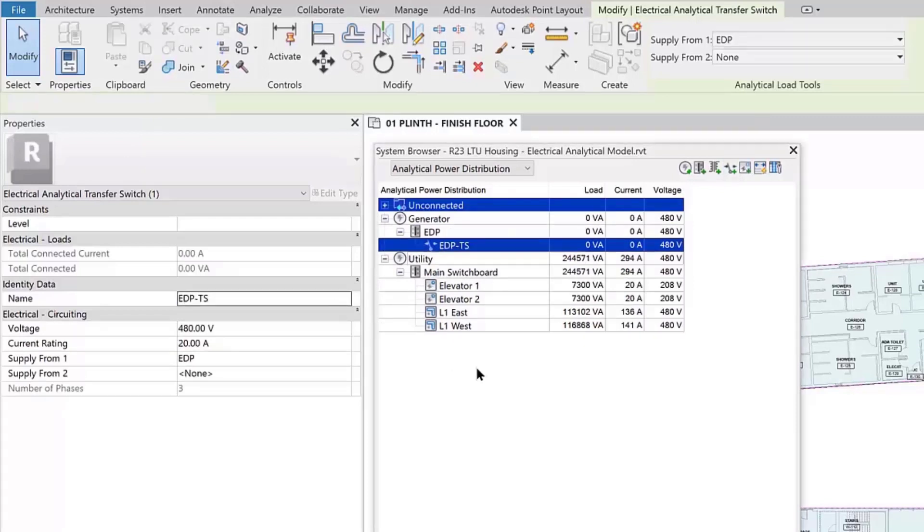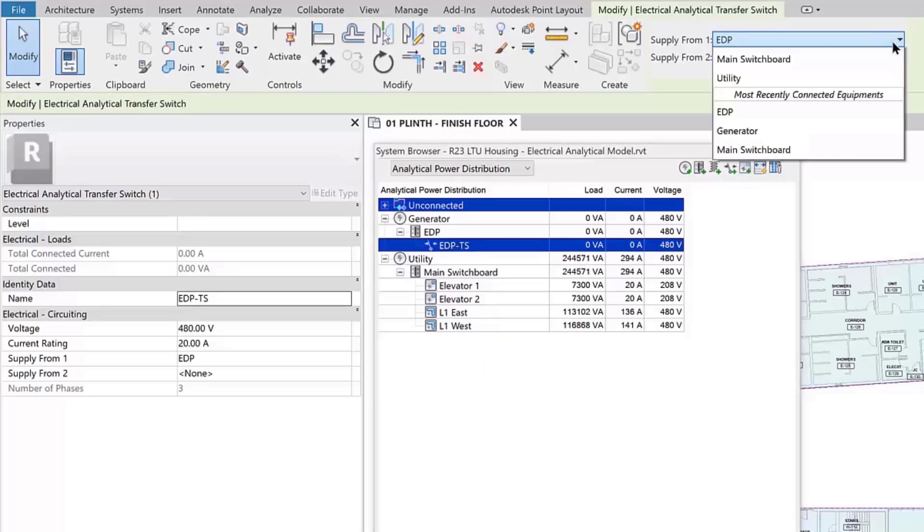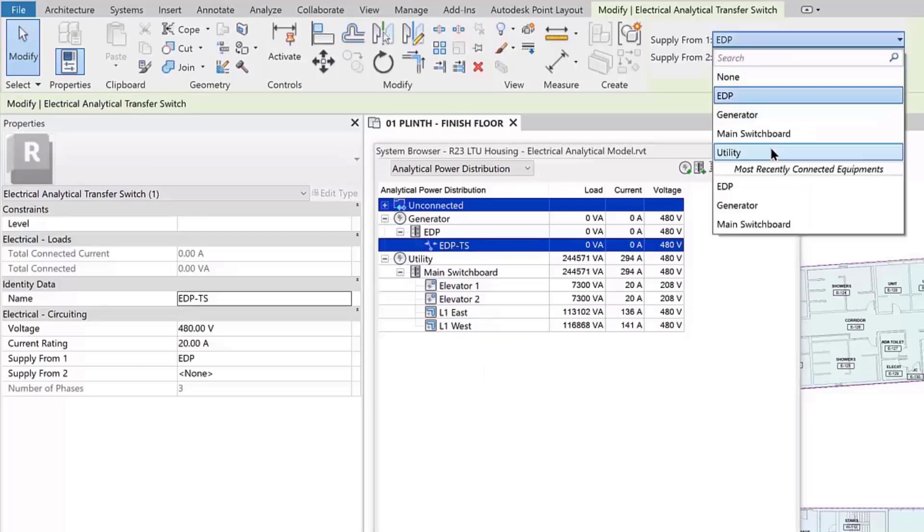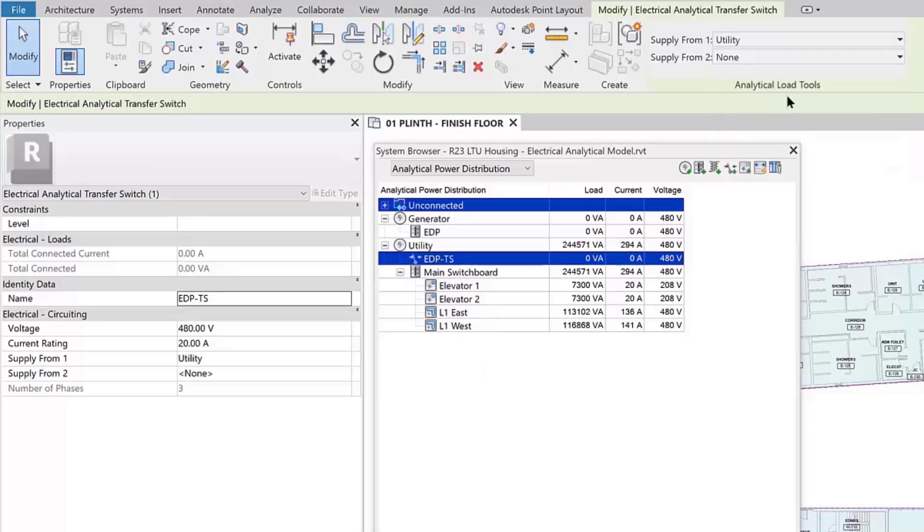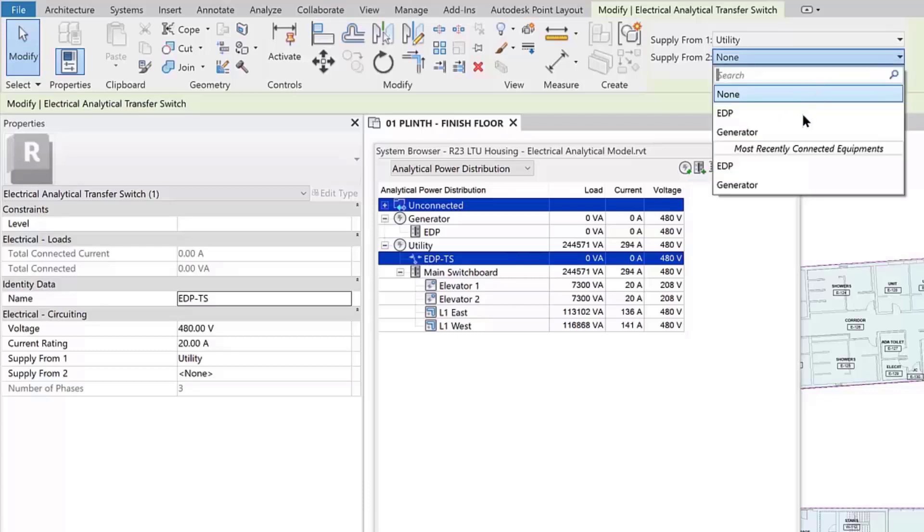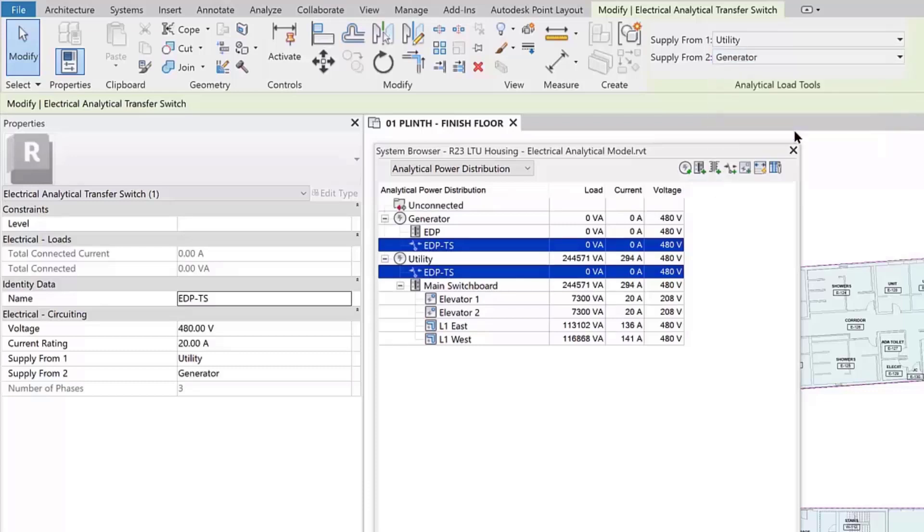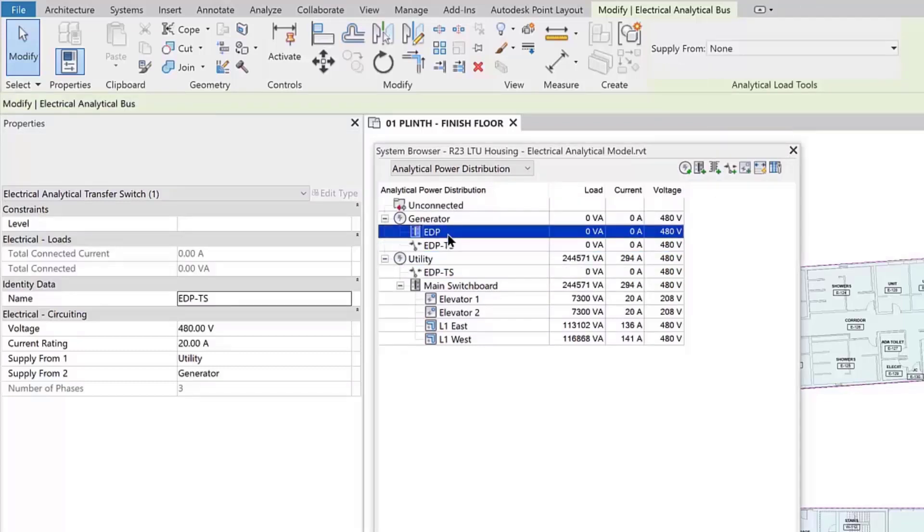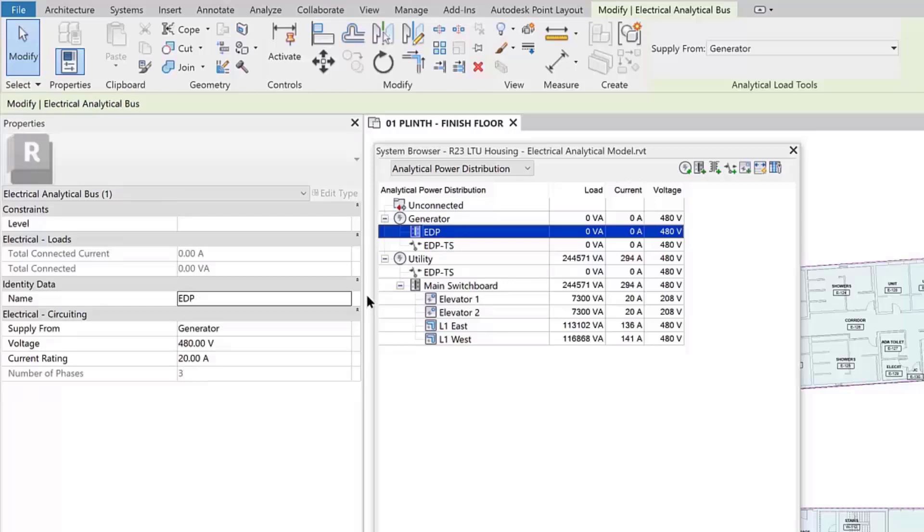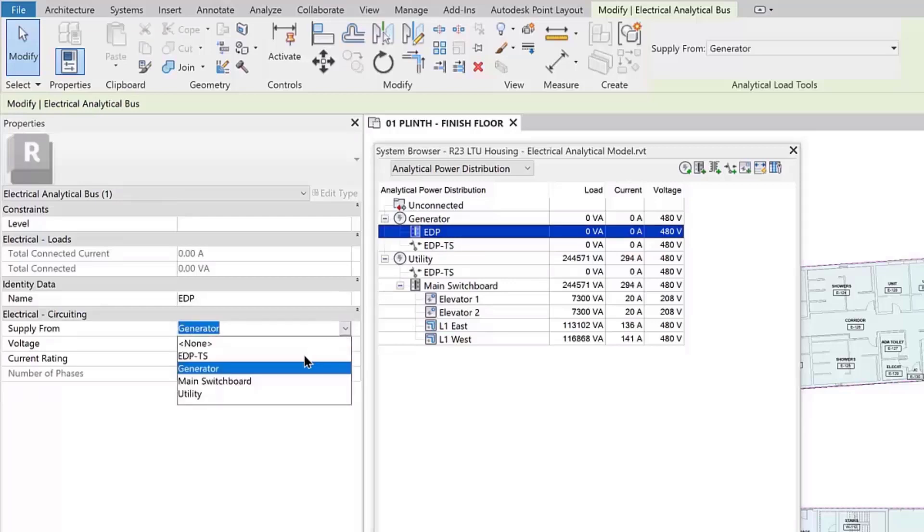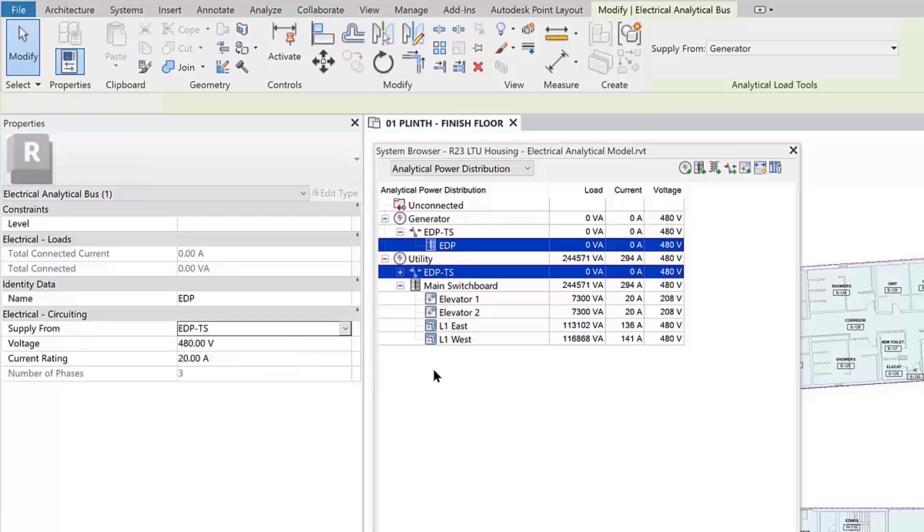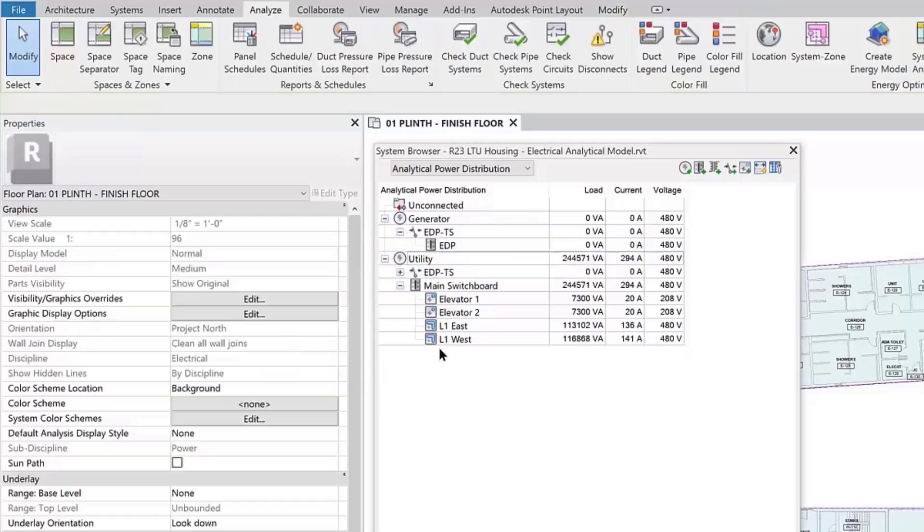You can modify the system hierarchy by selecting an analytical element and setting its supply from property on the Analytical Load Tools panel, on the ribbon, from the properties palette drop-down list, or from the right-click menu in the system browser. Transfer switches will appear twice in the distribution, once for each upstream source.